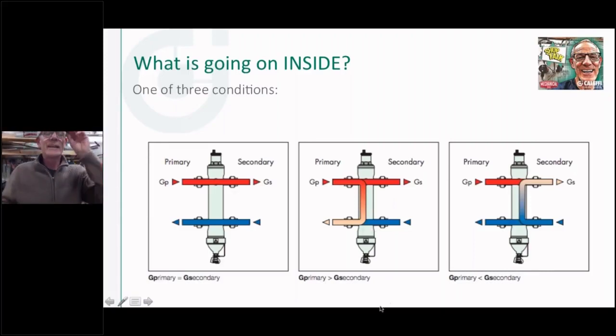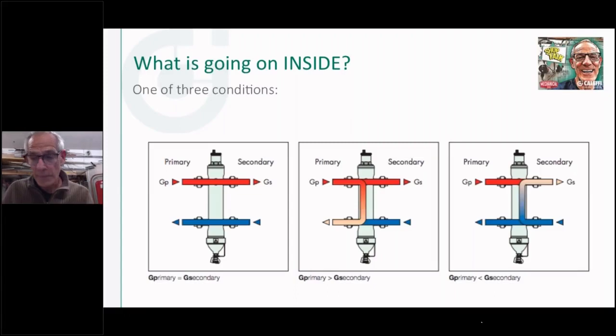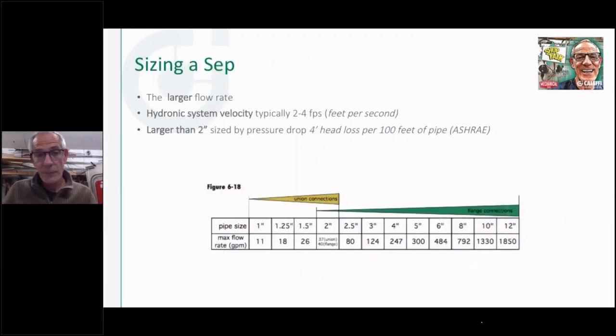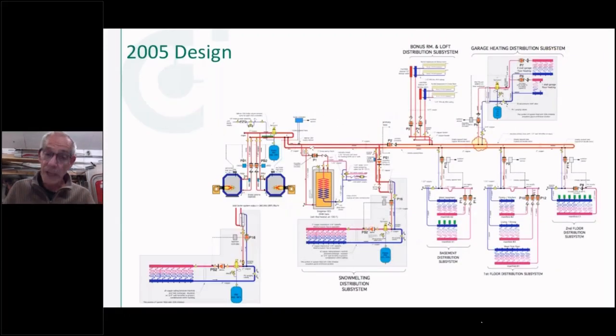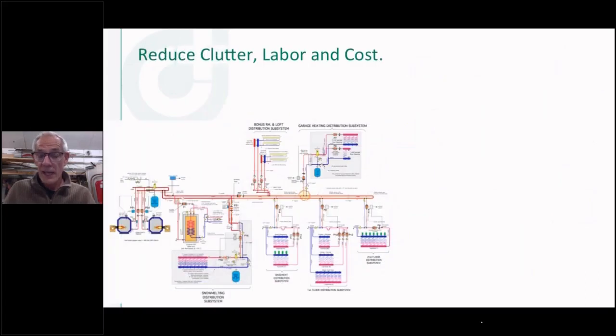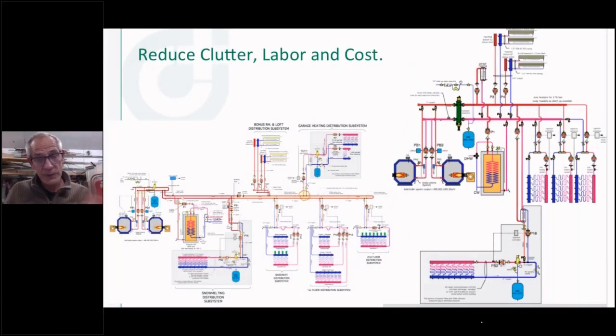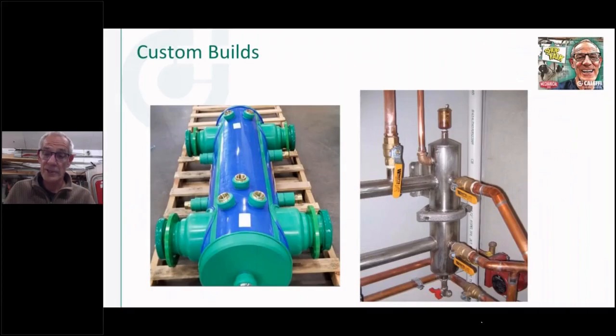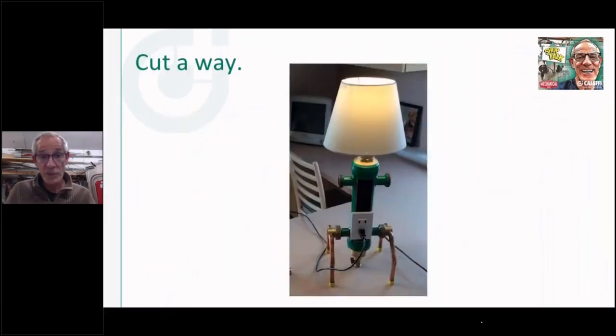So yeah, it has more to do with expansion tank, and I don't want to confuse you too much on that, but we want to pump into these high pressure drop boilers. And if we're going to pump into the boiler, we've got to pump away from the expansion tank. And that's why it becomes more critical that we get that relationship proper, the expansion tank to the circulator.